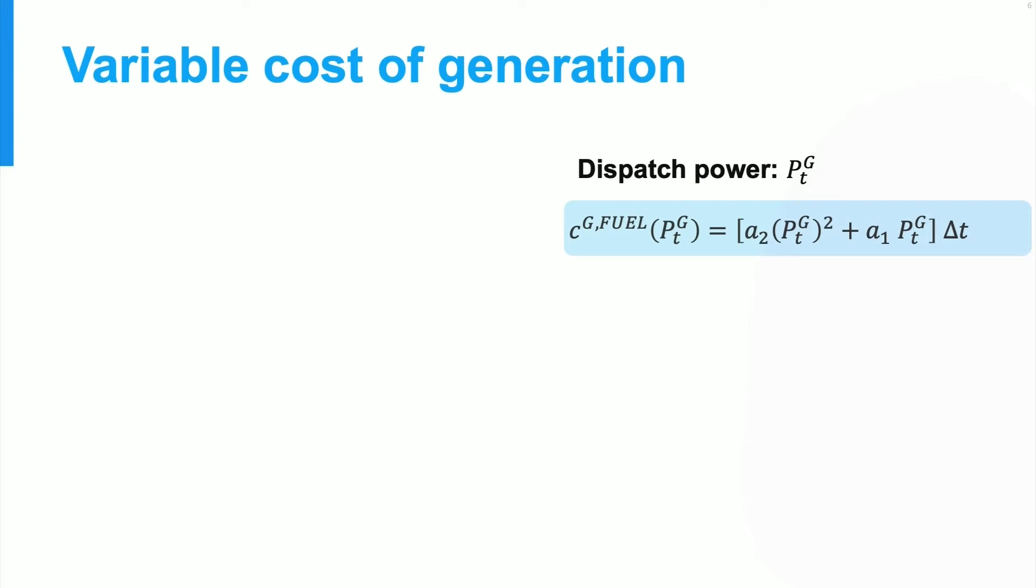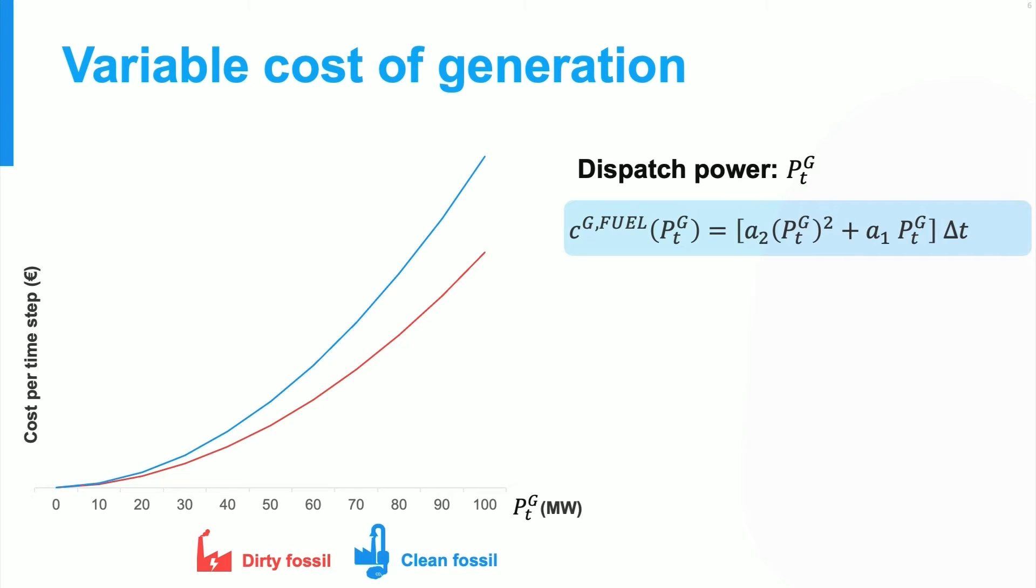Now in terms of this dispatch variable, we can define a function for the cost of generation in the time interval. And it's common to use a quadratic function for this purpose, with coefficients a1 and a2 that we must define. You can see such a curve here on the left for the dirty fossil plant. In this case, the generator becomes less efficient at high power levels. So you can see that this cost curve becomes steeper for each additional megawatt produced.